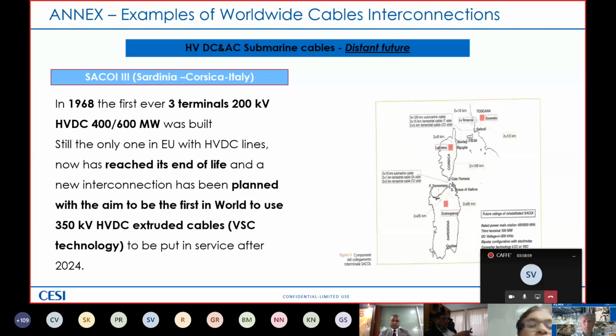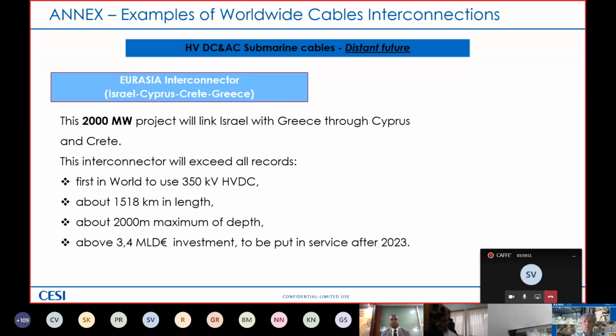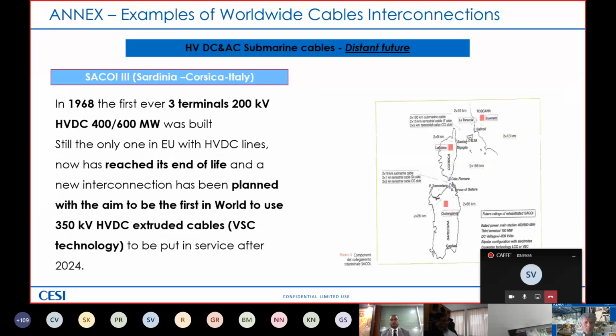In the near future, we have to work in Italy on the Sardinia to Corsica to Italy connection. This was the first one put in service, in 1968, and connects Sardinia, that is Italy, Corsica, that is France, and from Corsica to Italy again. But as I said, this connection is still working, but it is more than 50 years of age. It suffered different failures along the years. So Terna and RTE decided to install a new 350 kV HVDC extruded cable interconnection because this whole system has almost reached its end of life. And this will be installed starting from 2024, yes.